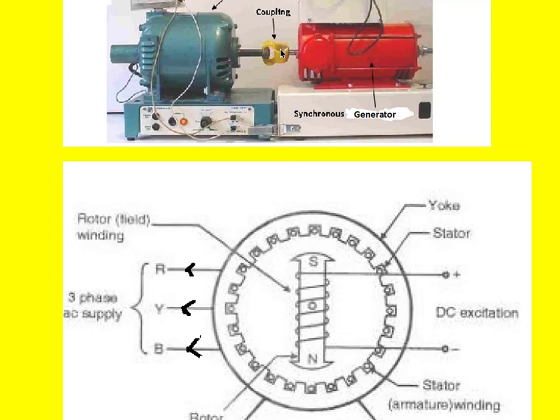The mechanical input comes from the motor shaft through the coupling. Once the motor is started, the rotor starts rotating and the rotor already has magnetic poles over it — so it is as good as a magnetic field rotating within the stator. This magnetic field cuts the stator conductors placed in the slots or teeth of the stator. These windings are three-phase windings, so whenever there is a rate of change of flux linking with the stator winding, there will be an induced voltage, and because it is a three-phase winding we get a three-phase AC voltage.